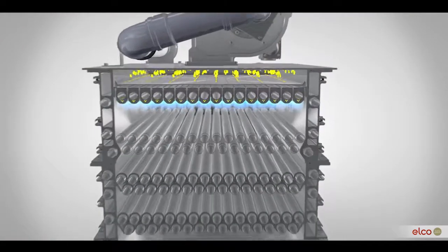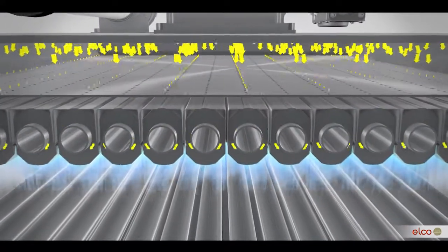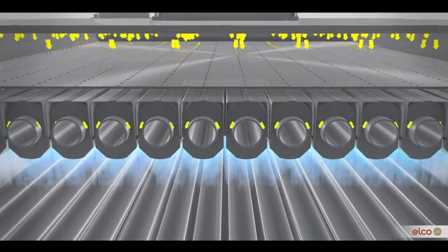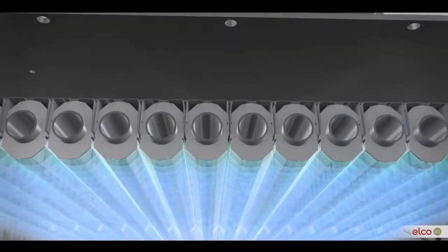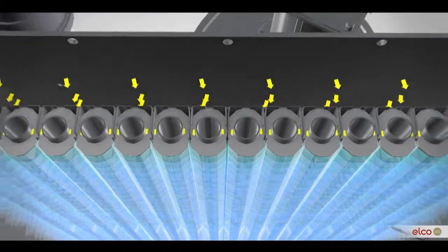The Elco burner is made of bimetal fin tubes and is an integrated part of the heat exchanger. The fins on the burner tubes act like many small nozzles to create a short flame. Having only a short flame reduces the time for nitrogen and oxygen to react and form NOx.